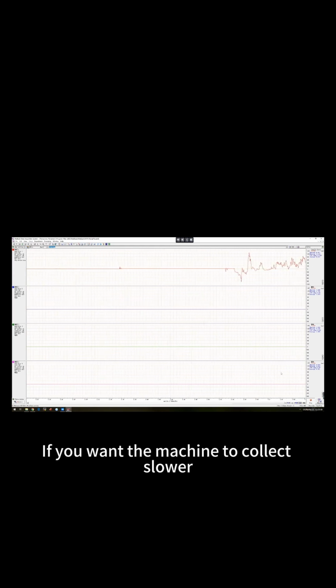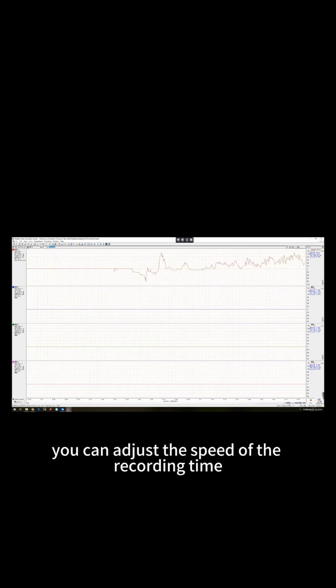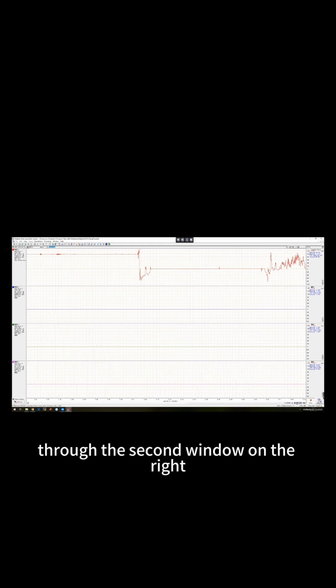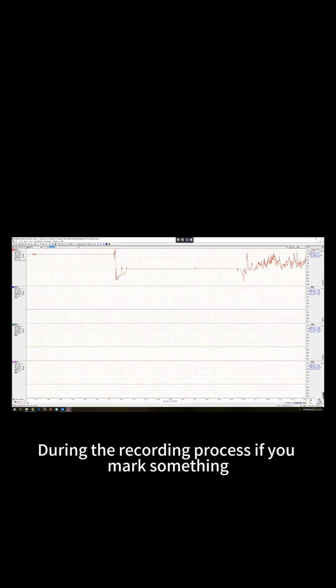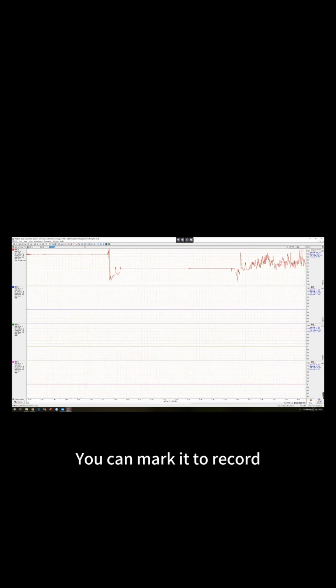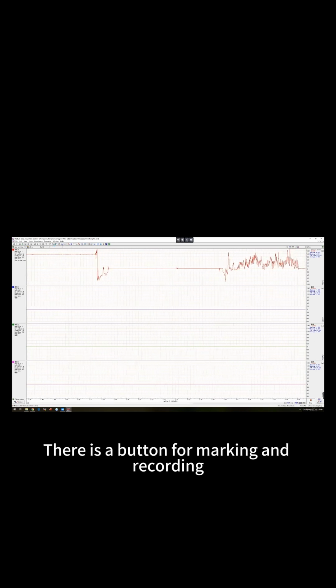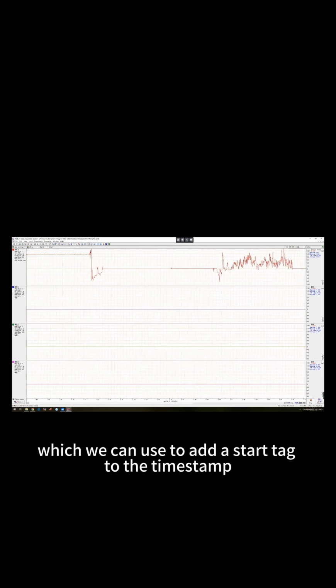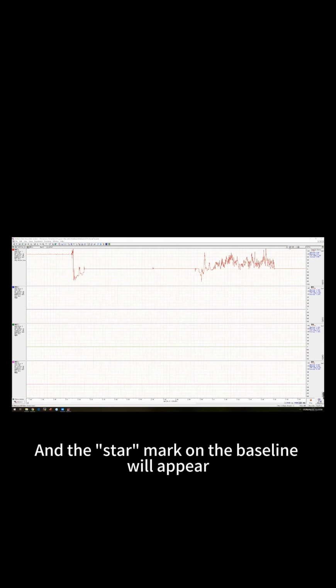If you want the machine to collect slower, you can adjust the speed of the recording time through the second window on the right. This is the tension setting. During the recording process, if you mark something, you can mark it to record. There is a button for marking and recording, which we can use to add a start tag to the timestamp. Click to add, and the star mark on the baseline will appear.